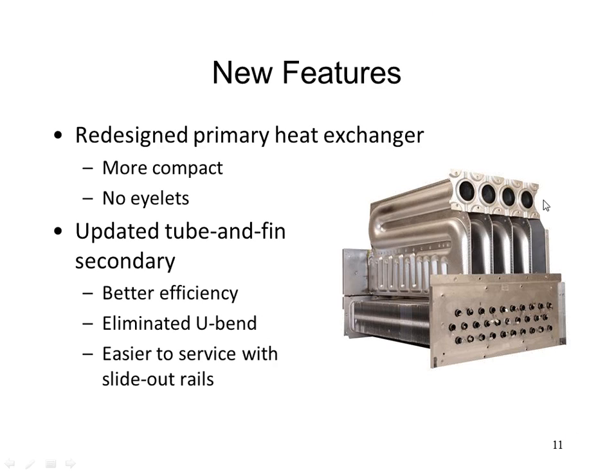But the top side of that heat exchanger, where you see the 4 inlets there, that's where the 4 flames are going to be blowing into this guy. You could have anywhere from 3 to 7 cells. This happens to be a 4-cell heat exchanger. So that's going to be where my combustion's happening. The flame's going to go into those tubes. It's going to make a 180-degree turn, come back to the front of the furnace, make another 180-degree turn, come through that rest of that primary heat exchanger, come out to the back side, make another 180-degree turn, and then come through each of these individual tubes here.